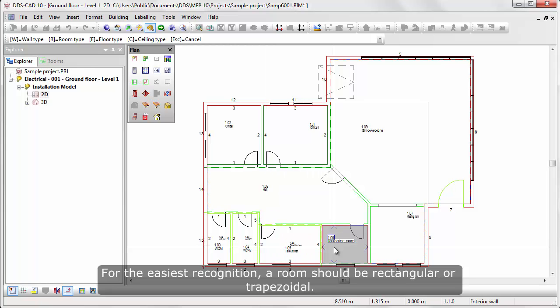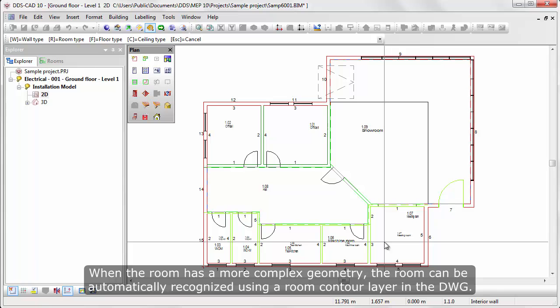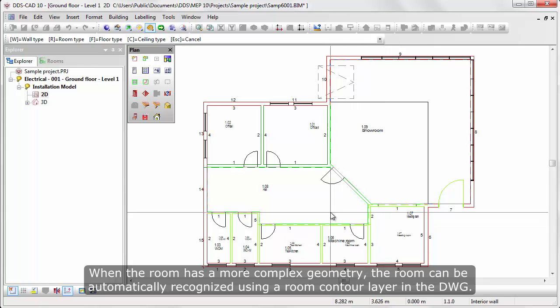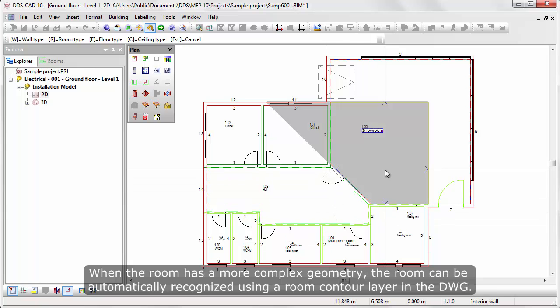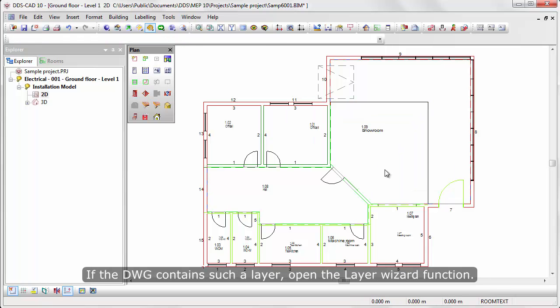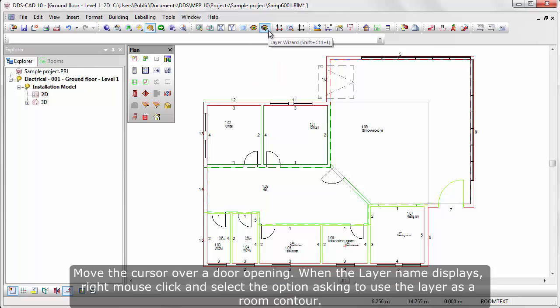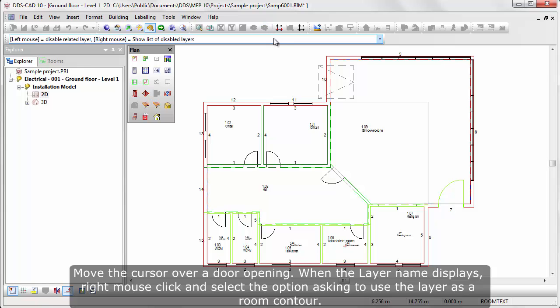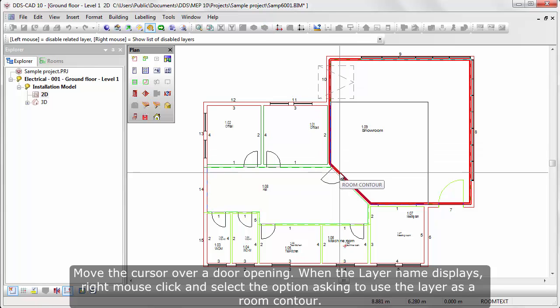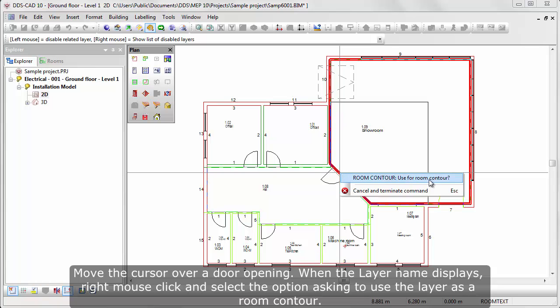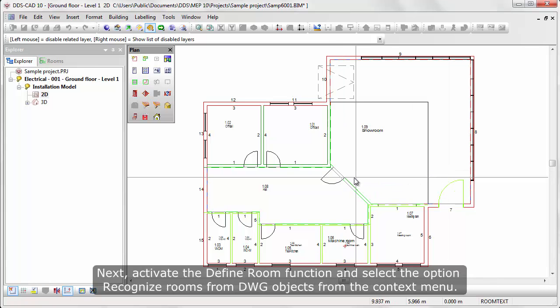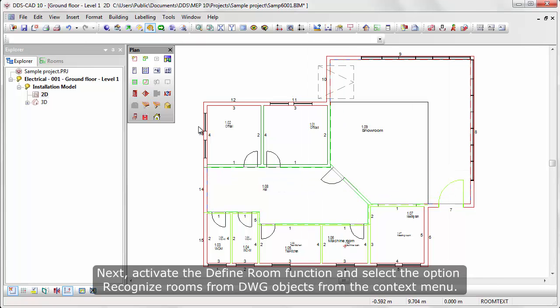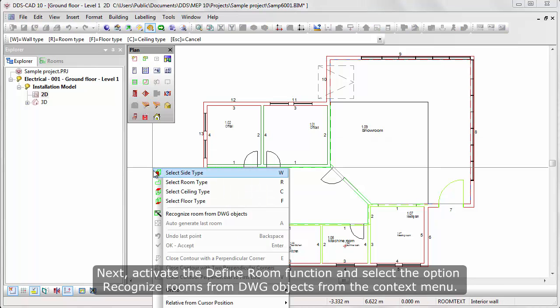For the easiest recognition, a room should be rectangular or trapezoidal. When the room has a more complex geometry, the room can be automatically recognized using room contouring layer in the DWG. If the DWG contains such a layer, open the layer wizard function. Move the cursor over a door opening. When the layer name displays, right mouse click and select the option to use the layer as a room contouring. Next, activate the define room function and select the option recognize rooms from DWG objects from the context menu.